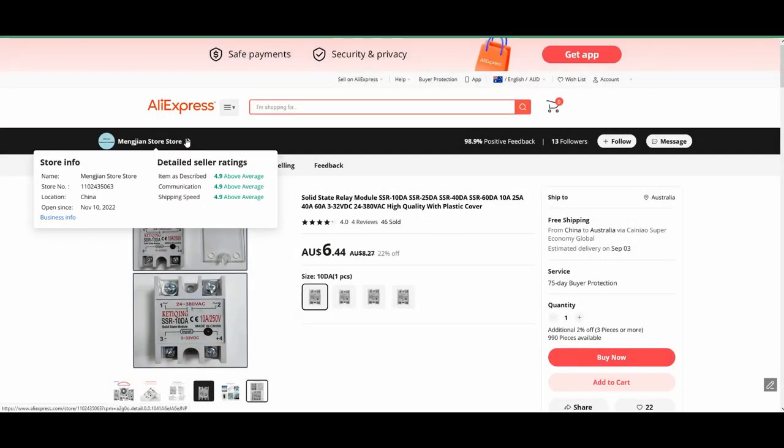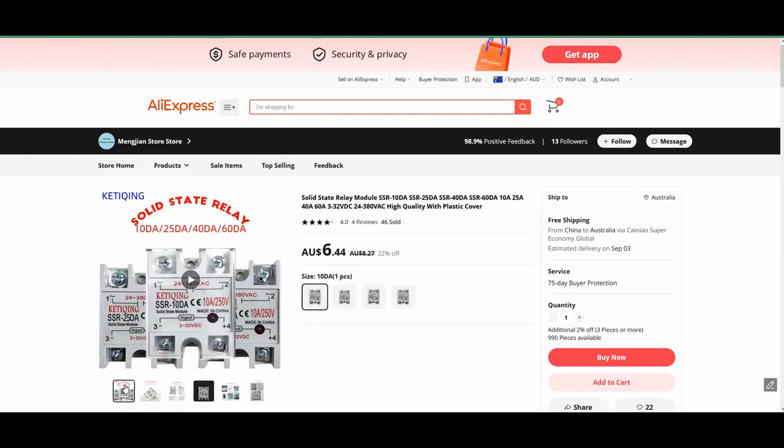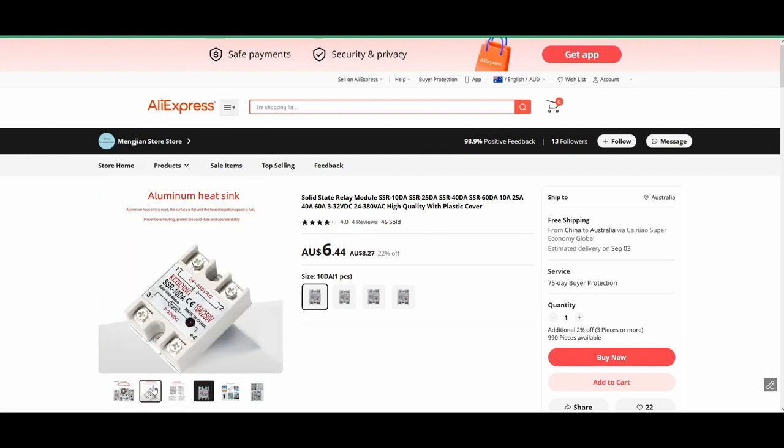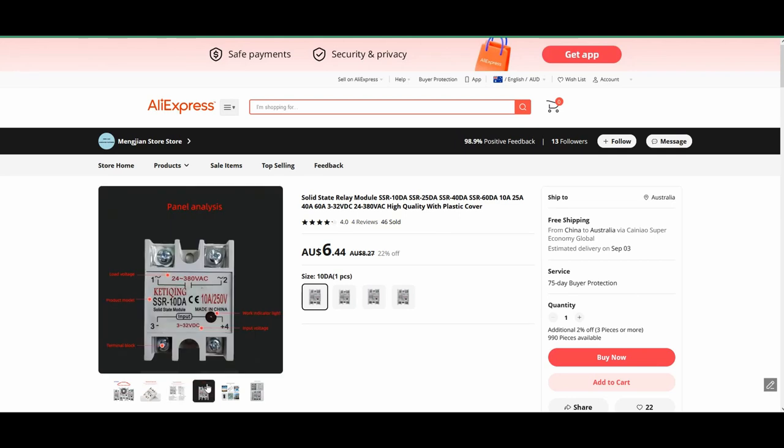I was given some solid-state relays, and considering their low cost point, I reviewed to see if they are better quality and would be a good replacement for the Fotek SSR from eBay that I commonly use, but which unfortunately are well known to be fakes with underrated triacs.